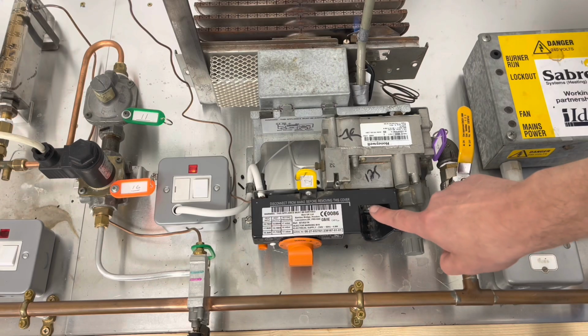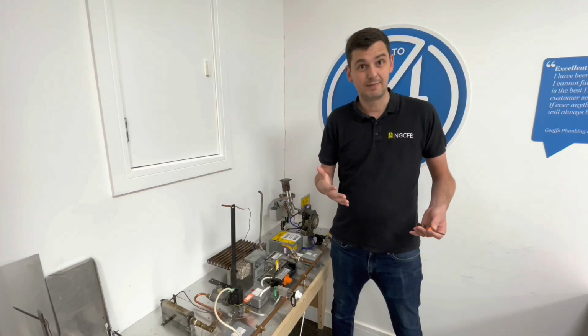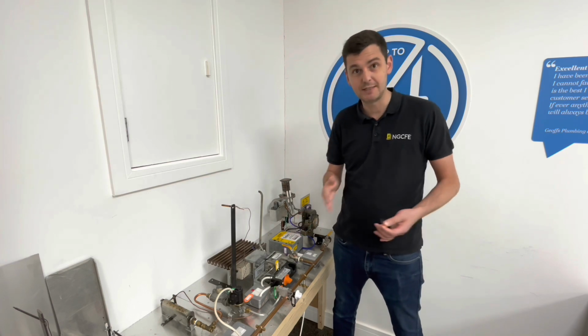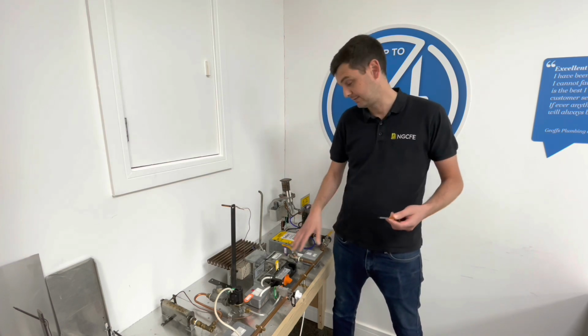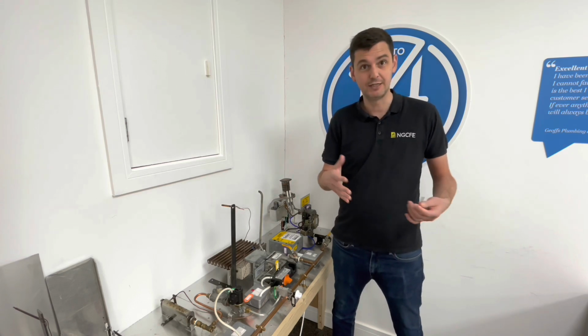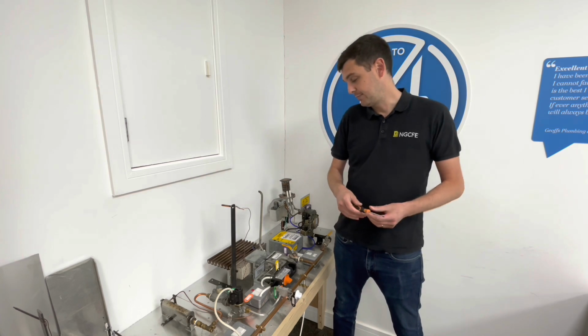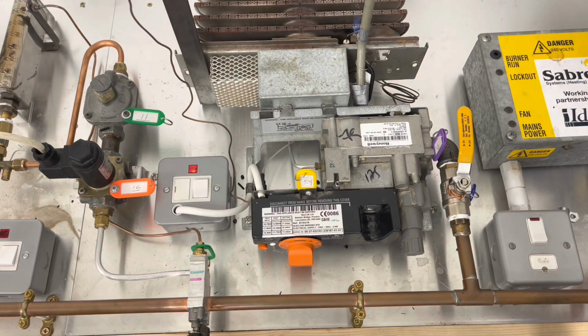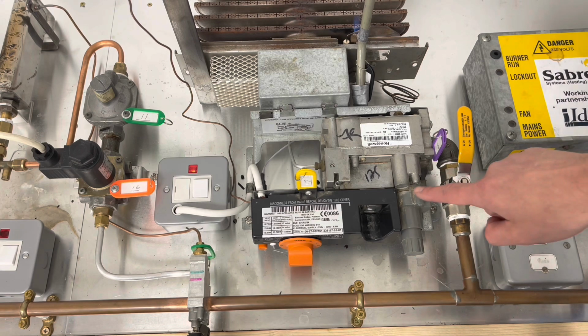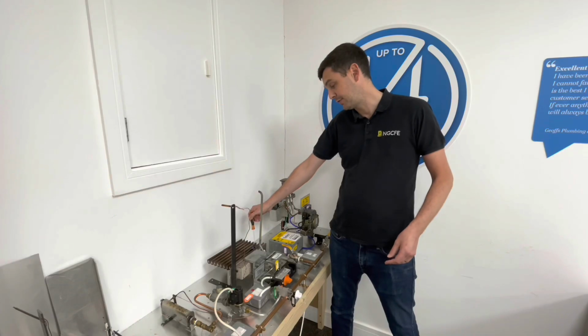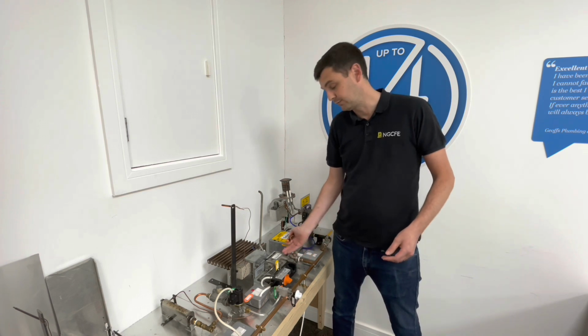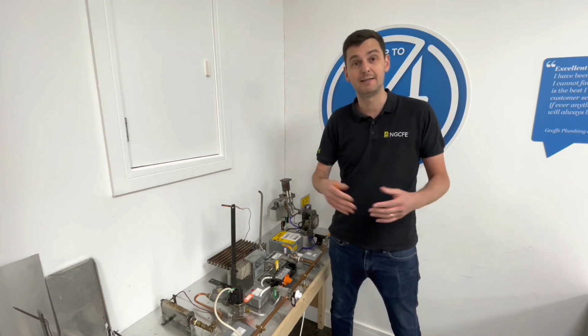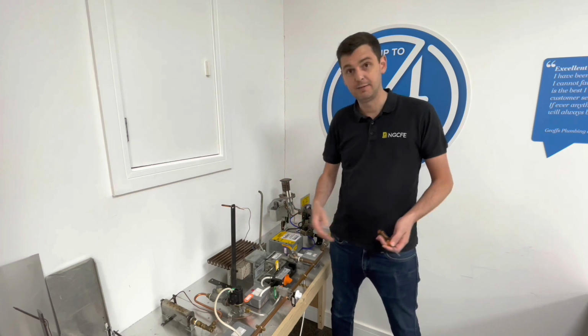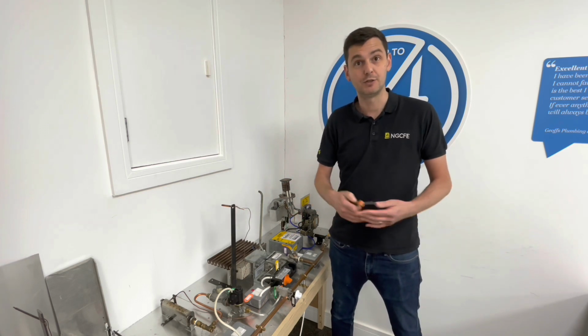The three main components are a regulator, which it uses to operate the outlet pressure. That's because it's range rated. We can generally set these appliances, we can set this valve, to give different outlet pressures depending on what we want to range rate the appliance to. As well as a regulator, it's also got a thermoelectric valve which we use to light the appliance. We've got a pilot light here with a thermocouple, and we've got a manual valve that we push in that will become energized when the pilot provides enough, the thermocouple provides enough current.